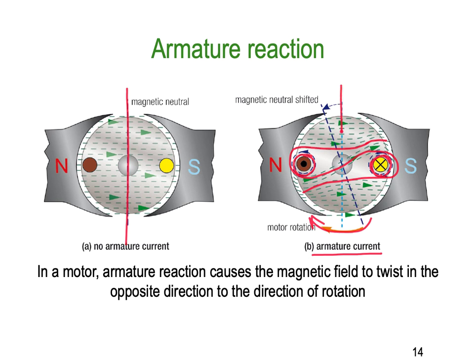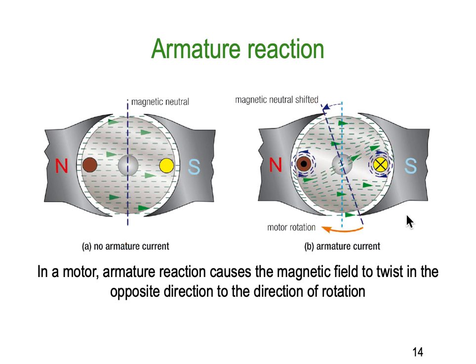This field shift creates a bit of sparking at the commutator and brushes. If this is occurring, instead of having your brushes mounted in their normal position, you literally just move them a few degrees around to align with the amount of armature reaction. Armature reaction just causes a bit of sparking which wears your brushes down a little more quickly. On most larger DC motors they have sliding brush casings for this very purpose — you can shift the brushes 10, 15, or 20 degrees around depending on how hard your motor is working.